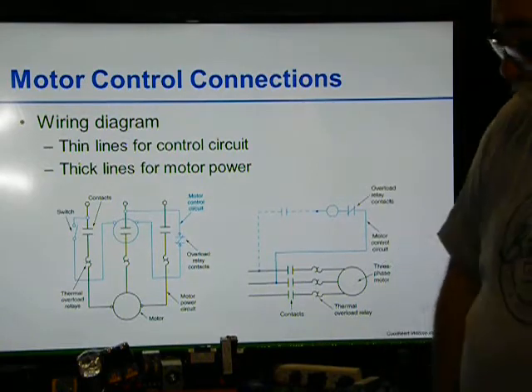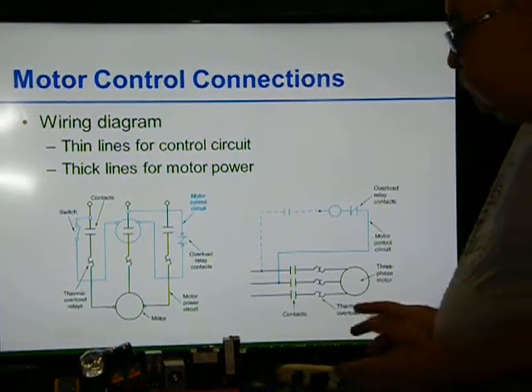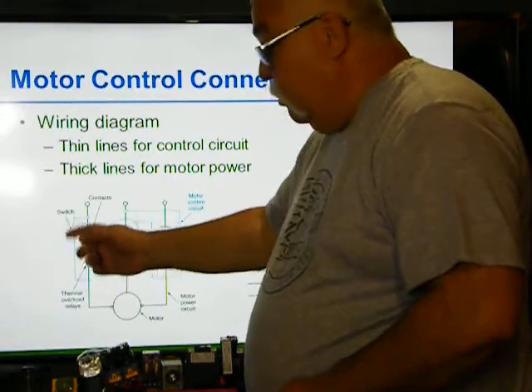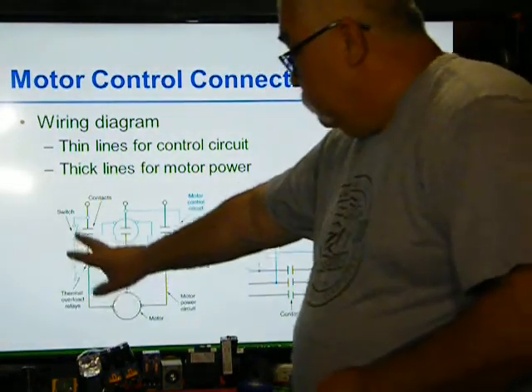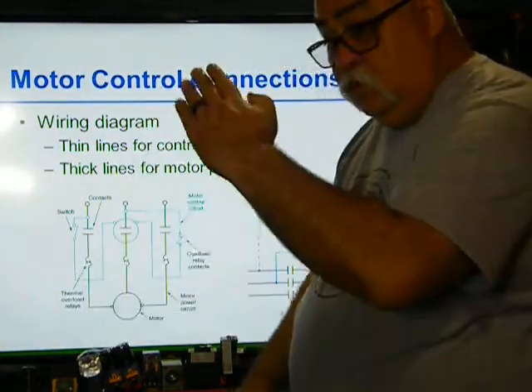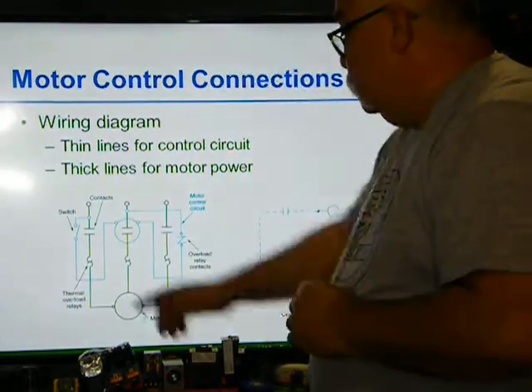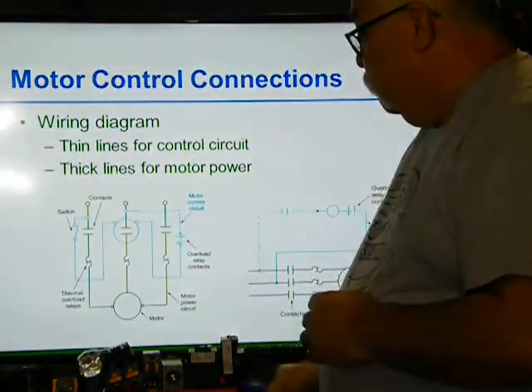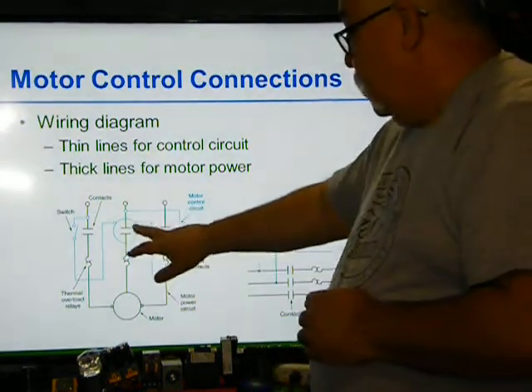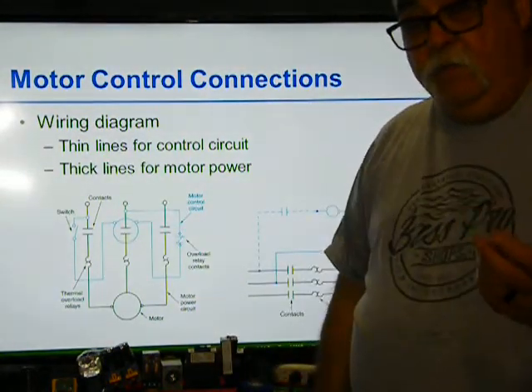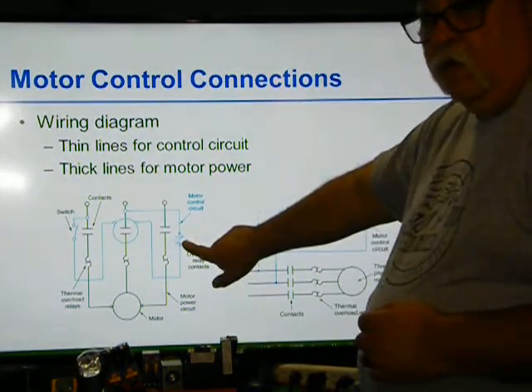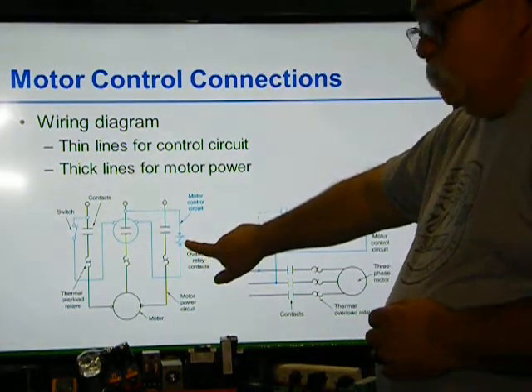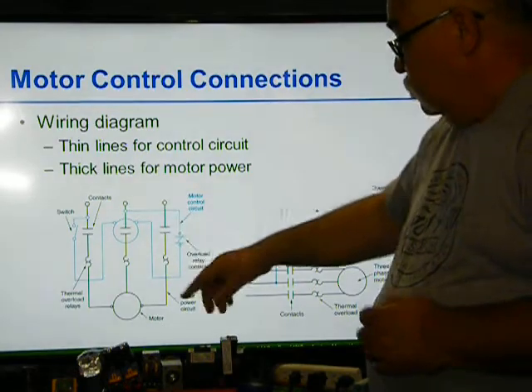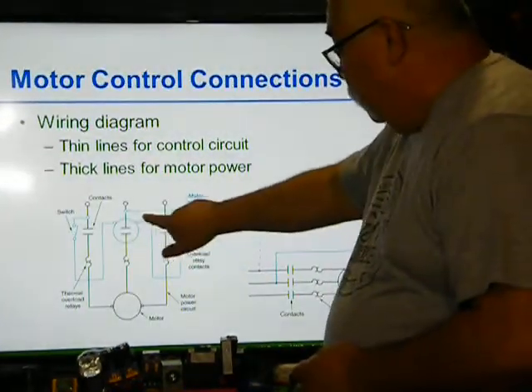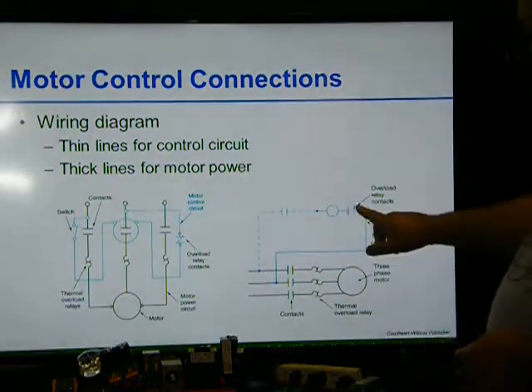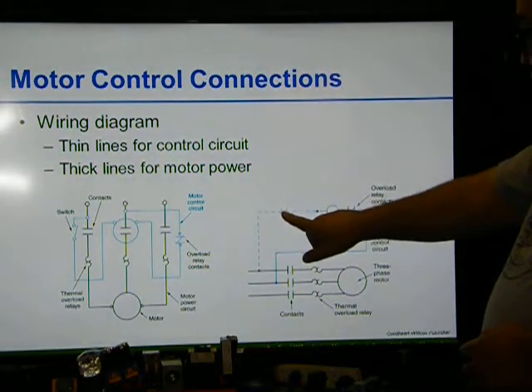Okay, so again, to this wire diagram, how does this work? This is a 2-wire switch. The switch is always shown in the off position. Okay, so there it is off because the switch is open. Once the switch closes, it provides power to here, motor comes on, motor works. These contacts are always shown in an open position. Okay, here's a closed contact. This is what a closed contact looks like. It's got that line going across. So if these were in the closed position, these would have a line going across. Okay, this one's closed. These are open.